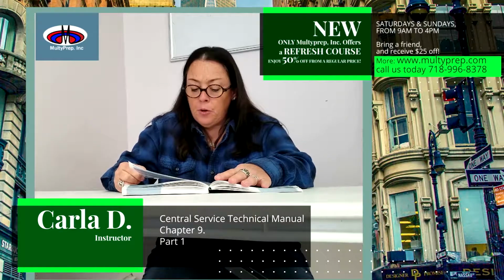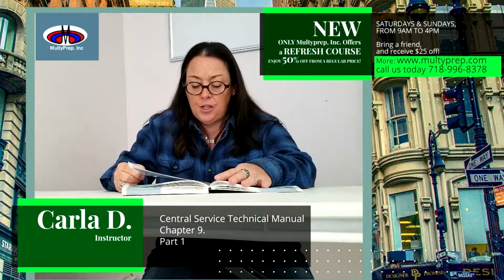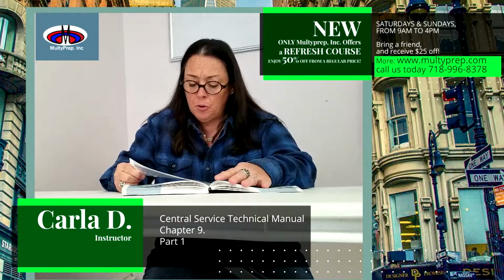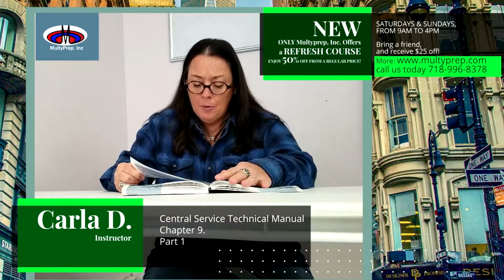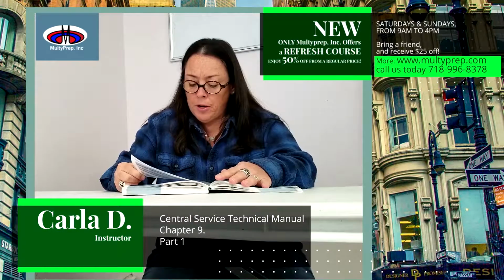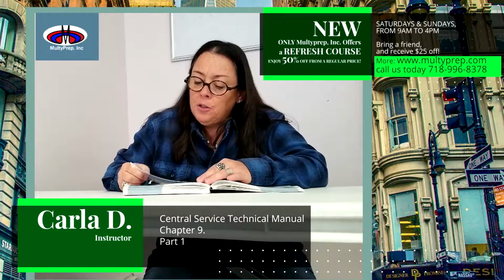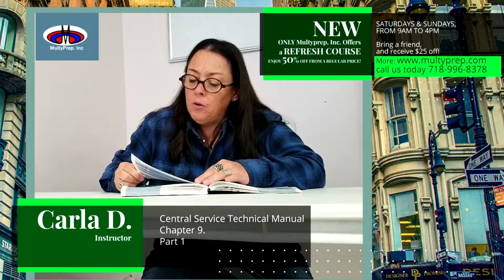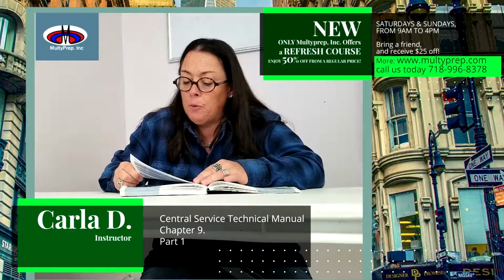Glutaraldehyde vapors increase whenever the solution is agitated, such as when it is poured into or dumped out of a soaking bin. Exposure levels for CS technicians during disposal can be reduced by adding a glutaraldehyde neutralizing agent to the solution prior to disposal. Consult state and local requirements and manufacturer's instructions for use for proper disposal measures.